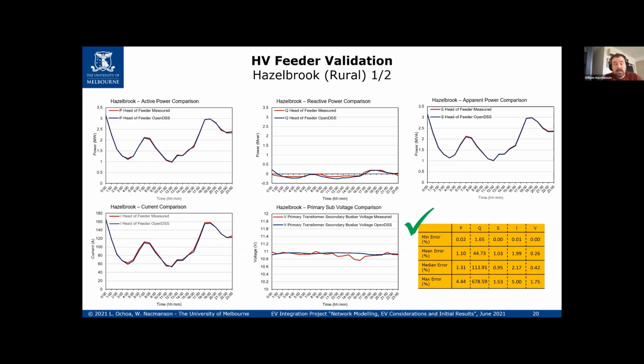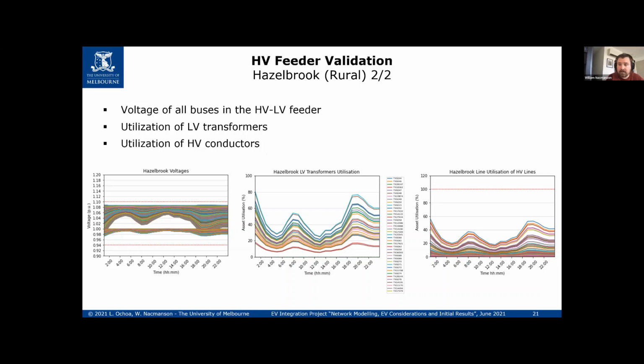And if we move on to the assets on the next slide, again, we can see the voltages. Now here you'll notice the voltage drops are a little larger. That large voltage drop you're seeing near 1.08 is at the LV transformers. There's a boost that most DNSPs employ on their LV transformers, bumping up to about 1.08 per unit. And then we have the voltage drop as you go down towards the end of the LV feeders for the customers. And again, if we look at the utilization of the assets, it's all looking sensible and what we expect.